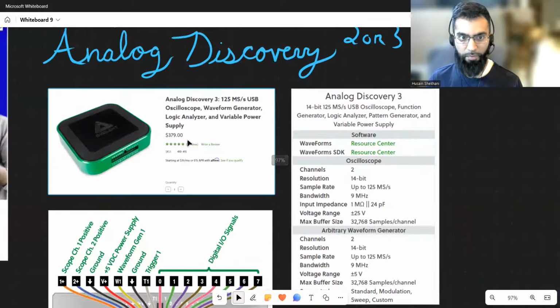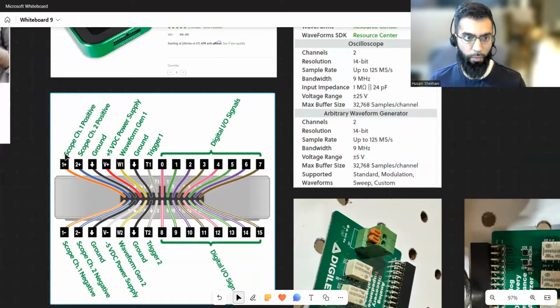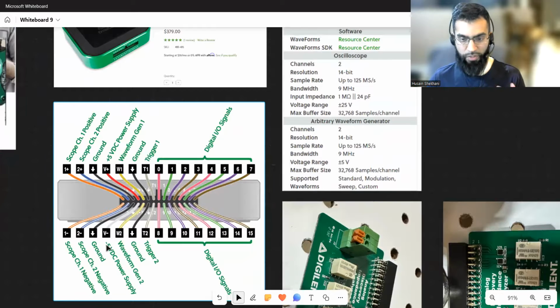It's set up like a general use device. As you can see here, it has two scope probes, which are semi-differential. It has power supplies, digital I/O, and two waveform generators. But the important thing, and why it is used as an impedance analyzer, is that it can measure two channels, voltage and current, and it can generate the waveform. If you can drive with a waveform of a known frequency, and measure voltage and current with two voltage channels, then we can measure impedance.